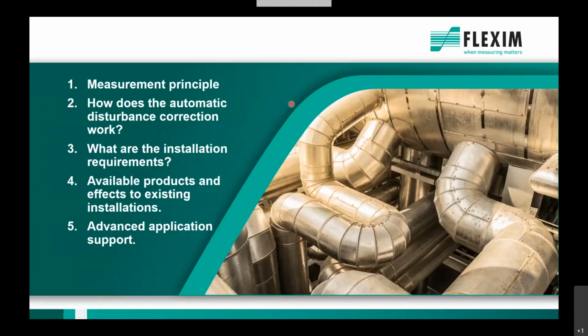Hello. Today we will talk about the advantages of using automatic flow disturbance corrections. This feature makes sufficient straight lengths almost meaningless, and installations can be done on the most convenient spot regardless of piping, especially for clamp-on meters, which are still used as a retrofit or for measurement points or replacements of existing flow meters. Sufficient straight lengths are rarely available. The automatic disturbance correction provides accurate readings even under unfavorable pipings. Literally speaking, clamp-on flow meters can be installed wherever you need a measurement.